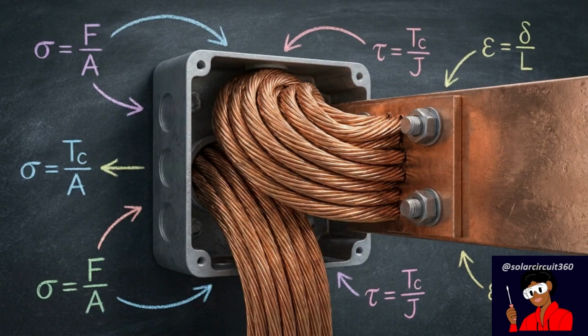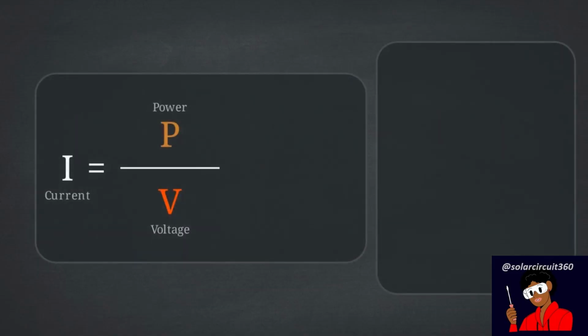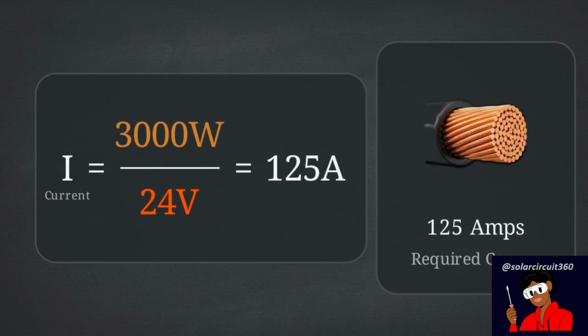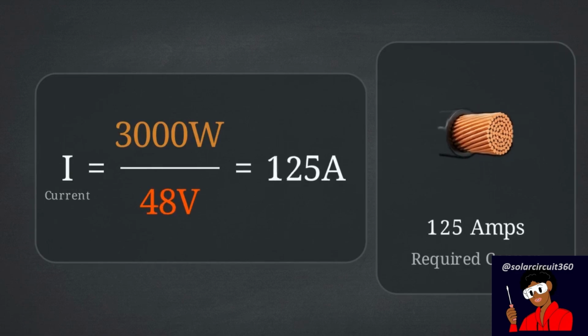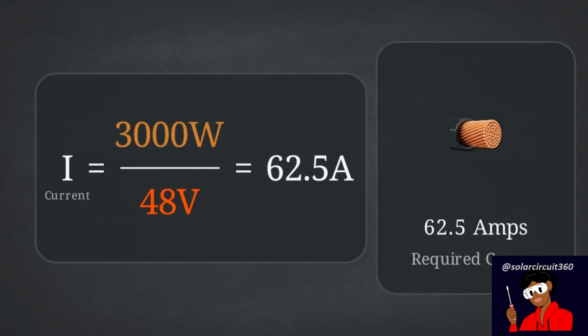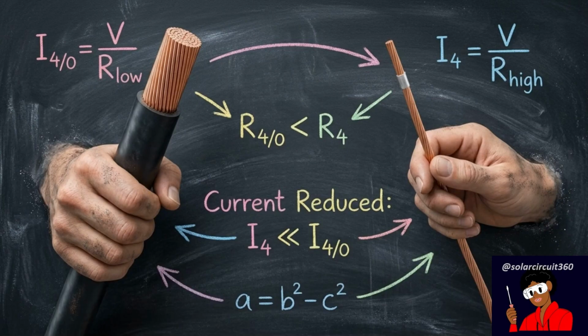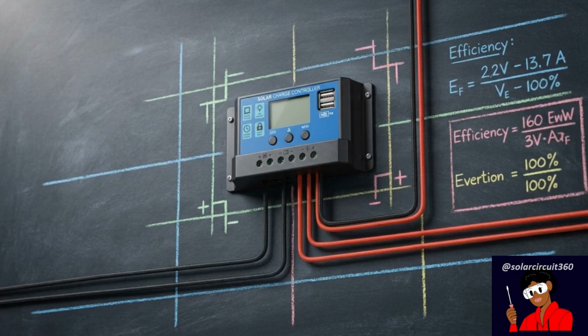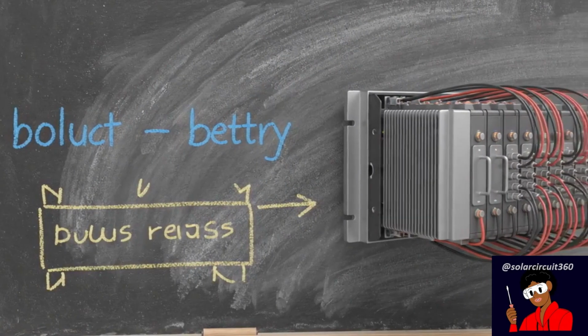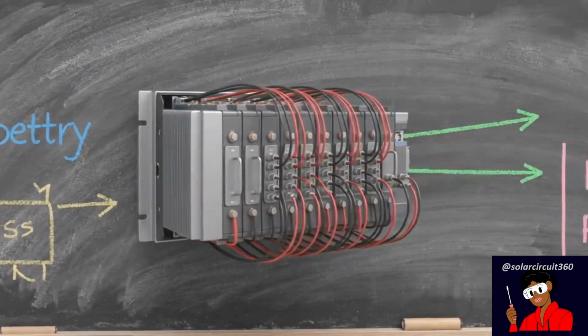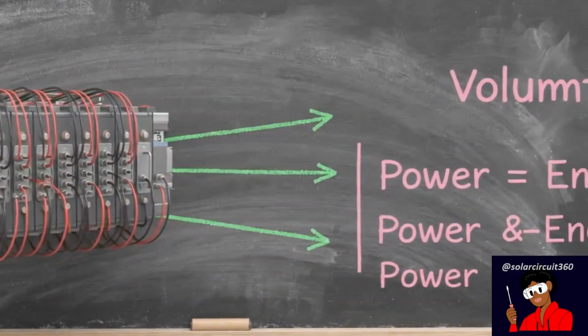If we recalculate the formula for a 24-volt system, the exact same 3,000-watt power load now draws only 125 amps. Pushing the system to 48 volts drops the required current down to just 62.5 amps. Reducing the continuous current to a quarter of its original value allows you to use vastly smaller wire. It makes cable routing flexible and creates a massive drop in the cost of raw materials. Scaling to high voltage acts as a literal space-saving mechanism, directly shrinking the physical footprint required to transfer energy.